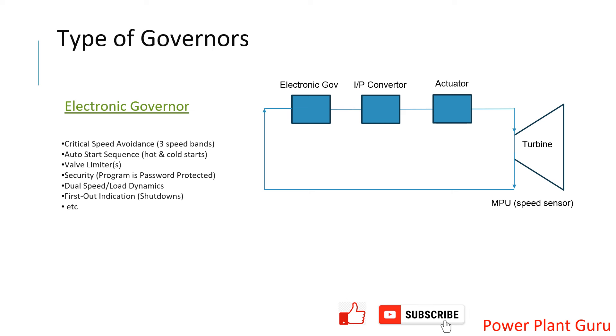Now coming to the electronic or I/P type of governors. Speed measurement in new turbines is done using a toothed wheel mounted on the steam turbine shaft. There are cuts or teeth on that shaft, and a probe positioned nearby looks at this as the shaft rotates.